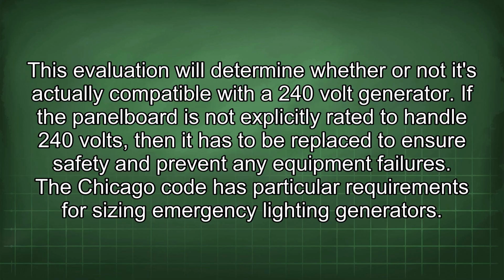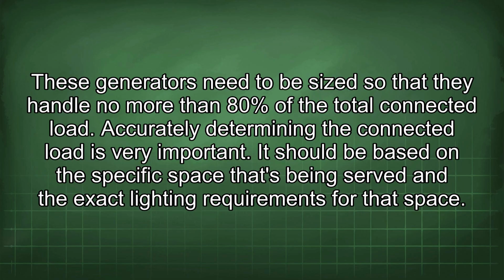The Chicago Code has particular requirements for sizing emergency lighting generators. These generators need to be sized so that they handle no more than 80% of the total connected load. Accurately determining the connected load is very important. It should be based on the specific space that's being served and the exact lighting requirements for that space.